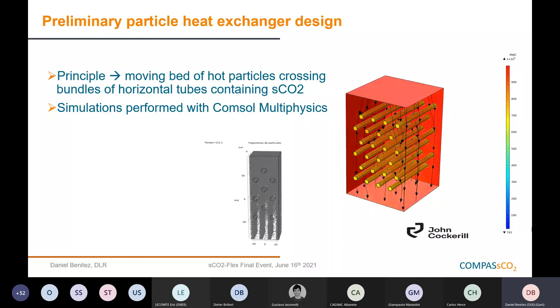Okay, so if we look closely at the parameters, the particles that flow into the heat exchangers will come in around 900 degrees C. And another important level is that the temperature of the supercritical CO2 coming out of the heat exchangers into the turbine will be 700 degrees. And the pressure, that we have a maximum pressure in the system of 265.3 bar, which is also very high, very demanding for materials.